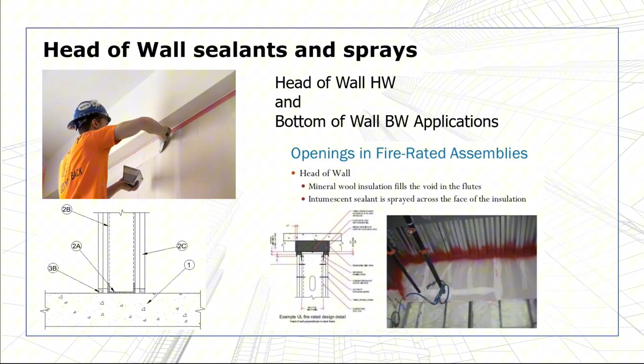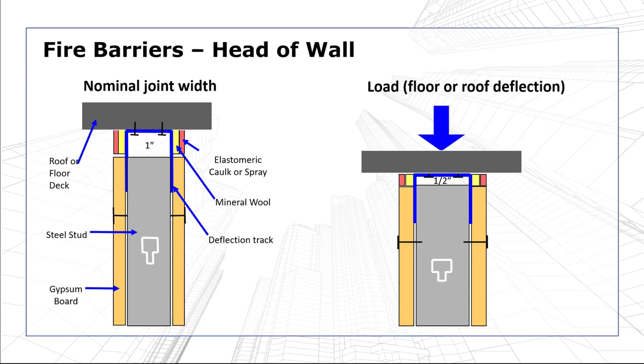This is a good example of what I'm talking about. So the floor on top, which would be the gray rectangle on the top left picture, would indicate a 1-inch gap that allows movement of that deflection of the floor material. And then on the right-hand side, it shows it being depressed down 1/2 of an inch. So it's compressed.